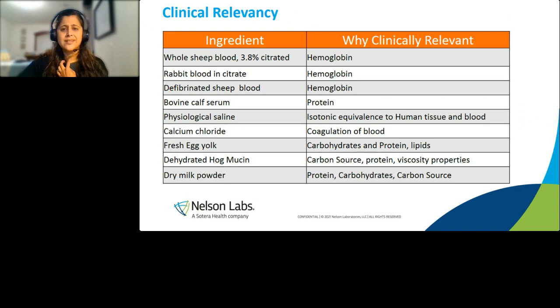Now, can we use any test soil? Probably not. So FDA does have an outline that any test soil you use, you have to scientifically justify the test soil and show how it's clinically relevant. And what I mean by clinically relevant is we have to show that the test soil we're using is what the device is seeing at the end, after the procedure has been performed, and what the users are seeing to clean. So the regulatory does make sure that the testing labs, when they're doing these validations, are working with the manufacturers closely to determine what kind of test soil we should be using for the validation and mimics the actual practices that are happening in the healthcare facility.